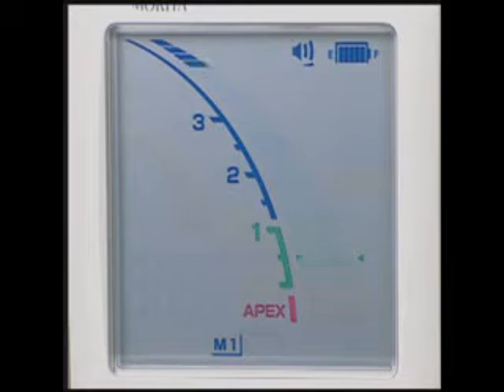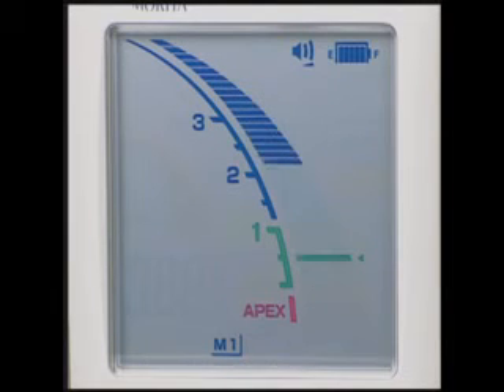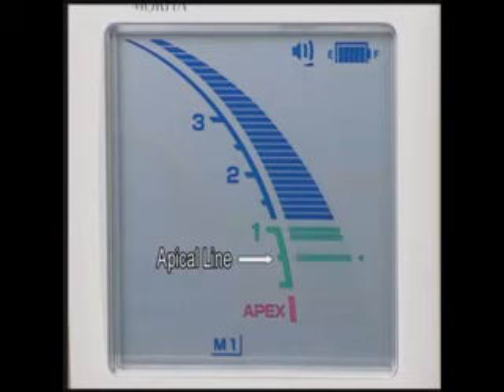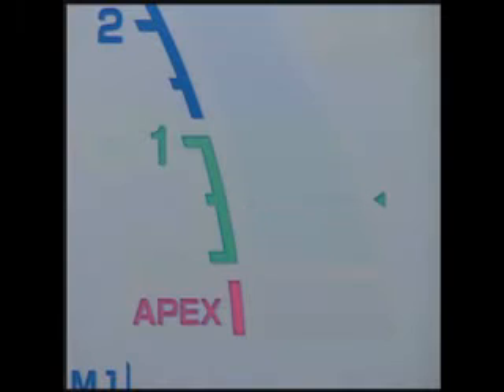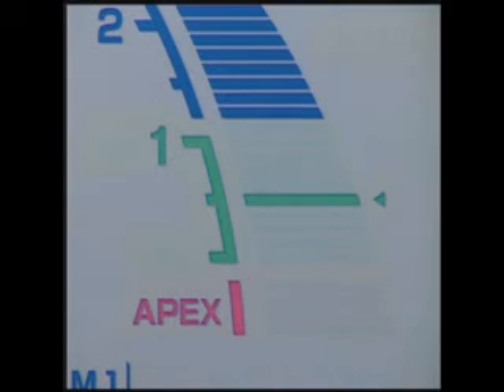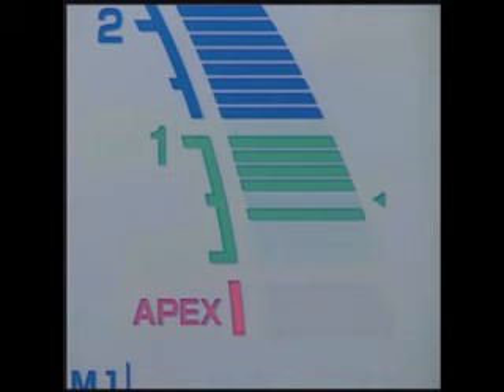The position of the file tip is shown by the canal length indicator bar on the display. The preset apical line flashes once the file is inserted into the canal. The indicator bar's 0.5 reading indicates that the file tip is in the apical constriction. As the file is advanced toward the preset apical line, a beeping sound indicates the position of the file tip. If the file tip passes the point indicated by the apical line, the alarm sound will change from beeping to a solid tone.